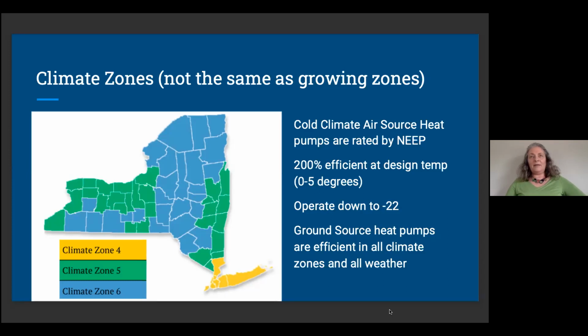You can look up the rating of each one on the NEEP list - that's the Northeast Energy Efficiency something or other, I can't remember what it stands for. At the design temperatures, which depends on the climate zone, they're 200% efficient. In other words, double the efficiency of electric resistance heating, which is what people think of when they think of electric heat.